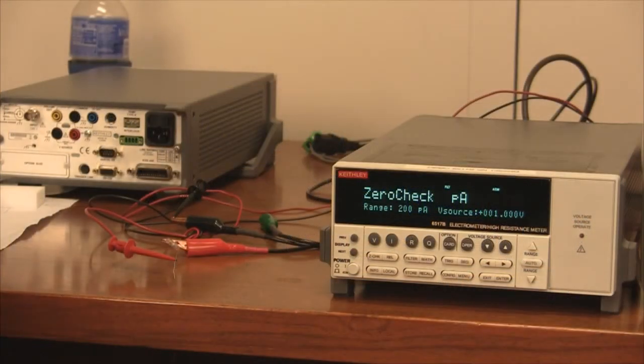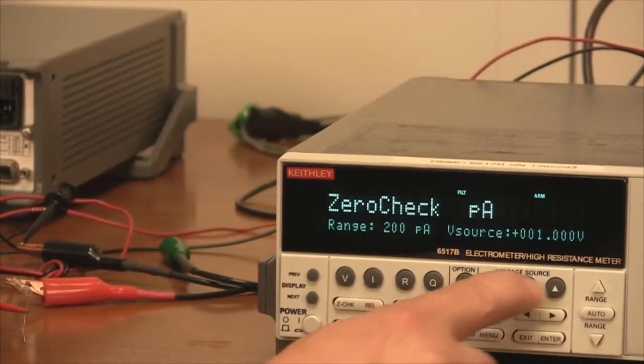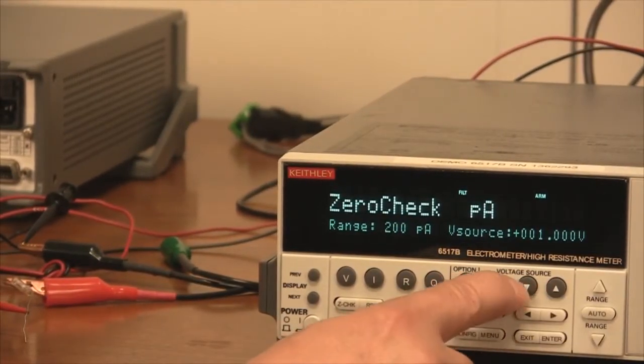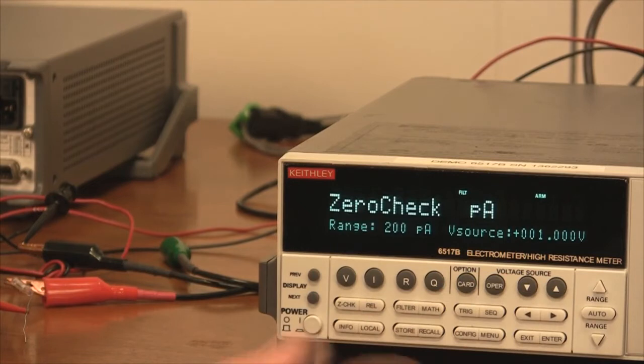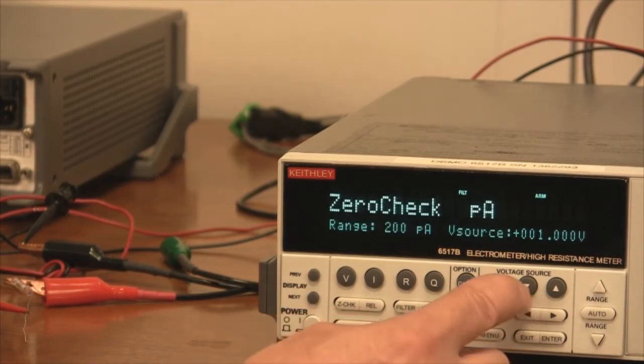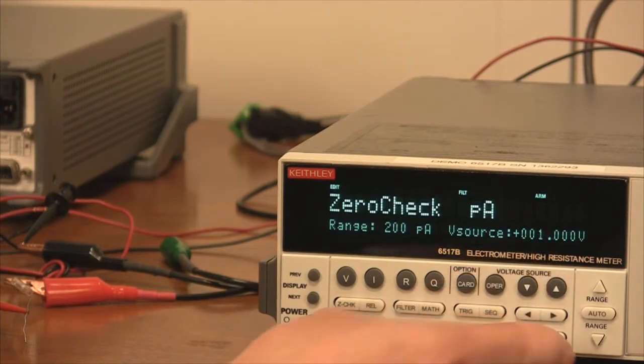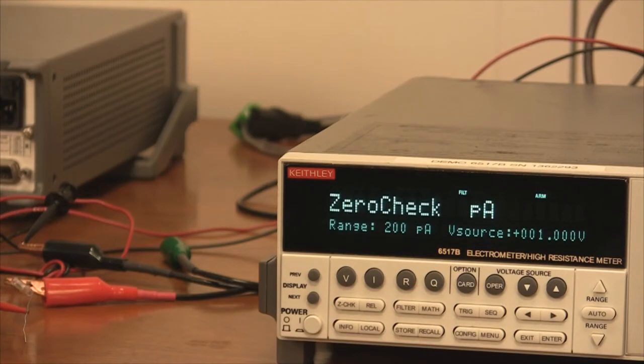With the connections completed, we can now set up the 6517B from the front panel. First thing we want to do is set up the voltage source. It's very simple, you go to V source. There are three buttons here: operate, up and down arrows. We're going to set it up with 1 volt. You can play around with it. You don't have to hit enter, it'll just stay there.